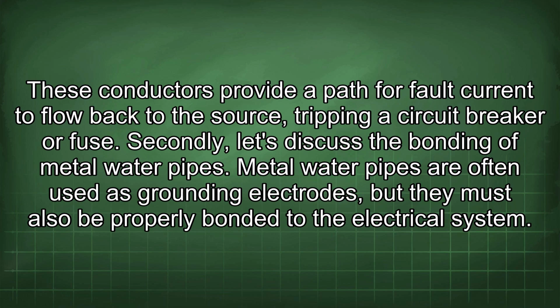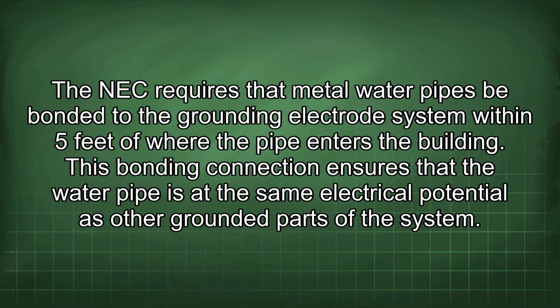Secondly, let's discuss the bonding of metal water pipes. Metal water pipes are often used as grounding electrodes, but they must also be properly bonded to the electrical system. The NEC requires that metal water pipes be bonded to the grounding electrode system within 5 feet of where the pipe enters the building. This bond connection ensures that the water pipe is at the same electrical potential as other grounded parts of the system.